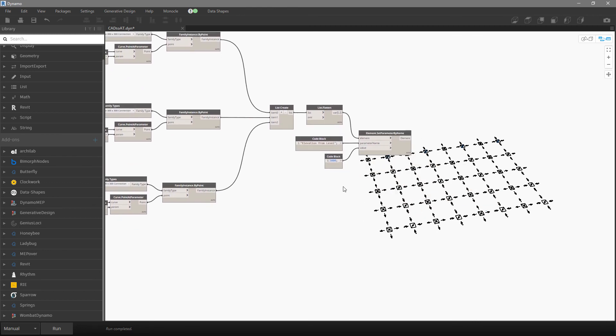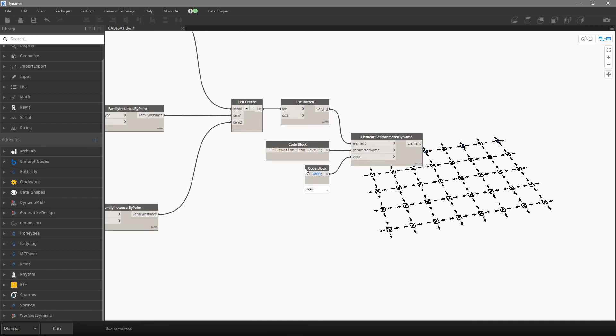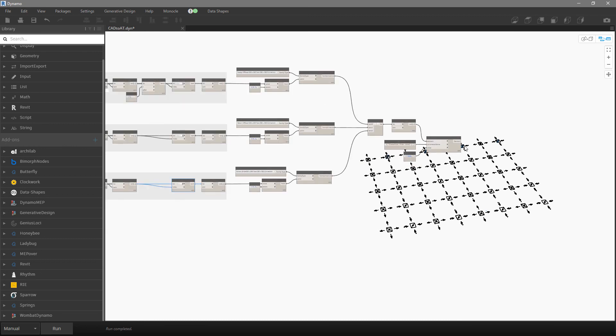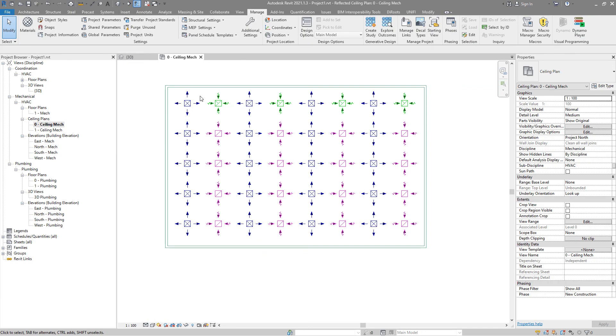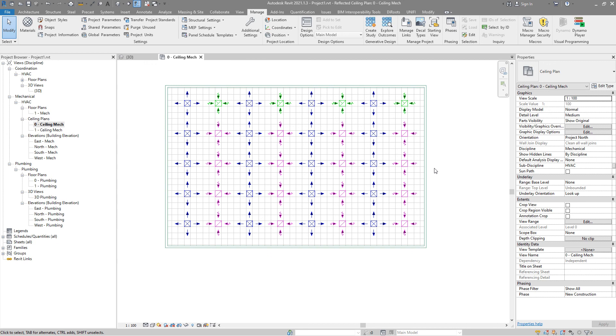Finally, because if we don't change the height of those diffusers they will all have height zero, I merged all those diffusers, flattened that list, and changed the elevation from level for those elements — I set three meters for all diffusers in this project. Overall, in a fraction of a second we created 40 elements, very quickly recognized positions from the AutoCAD, assigned proper family types, and that's it. Thank you for watching.